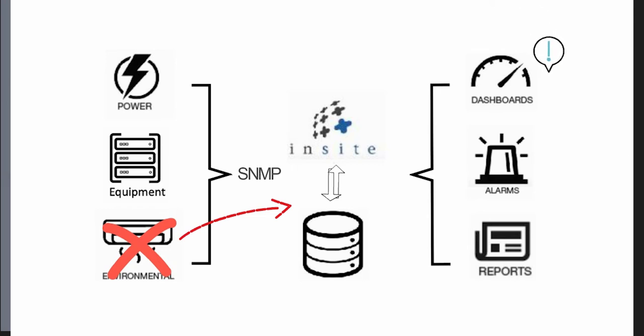So instantly we get a real-time readout in dashboards. On a screen in our engineering or master control or wherever it's relevant, we can actually start seeing visual alarms as they happen. Then we actually get triggered alarms, which can send out SMS messages and emails to the correct engineering staff to alert them that an issue has occurred that needs instant looking into. And then finally, it's logged into a report. So as a retrospective, we'll be able to see exactly what time and date this error occurred, and monitor the things that happened around it when this failure occurred.